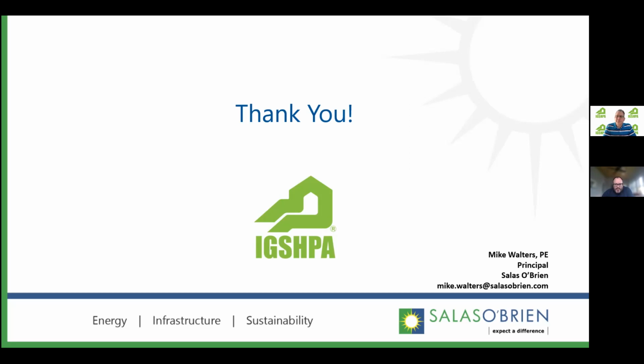The quick answer is that the most effective strategy we've found—effective meaning expedient and low cost—is to ask building owners to do slow resets of their supply hot water temperature during the coldest periods of the year, then expect cold calls and really understand how these buildings perform and whether they can meet certain criteria. That's far more effective than staring at mechanical drawings and doing load analysis to understand what the engineering tells you on paper.